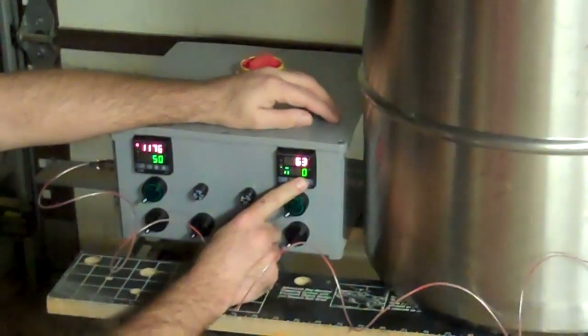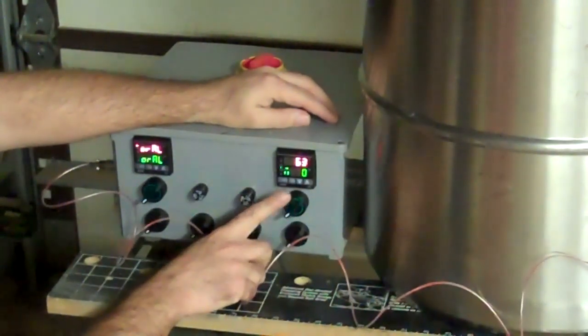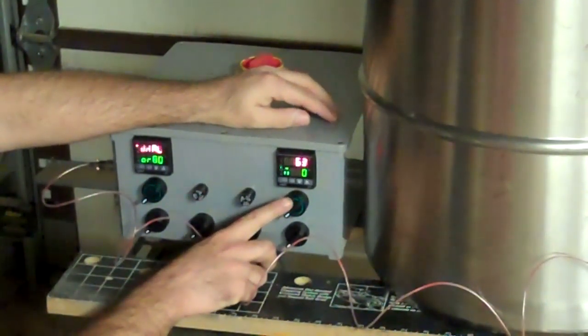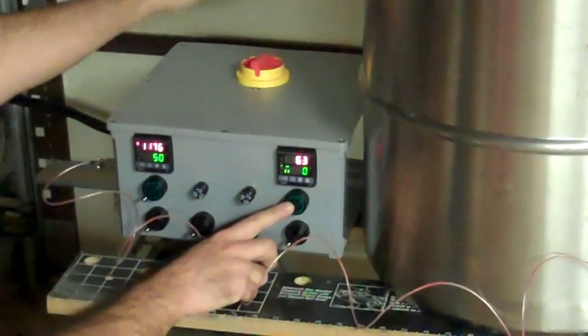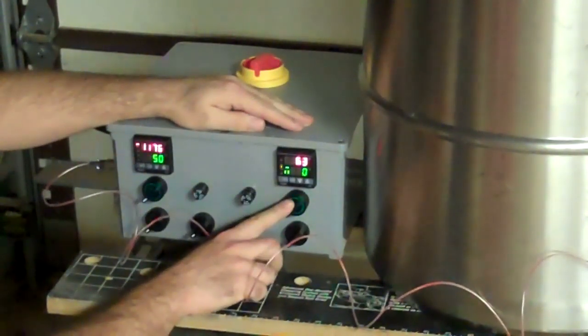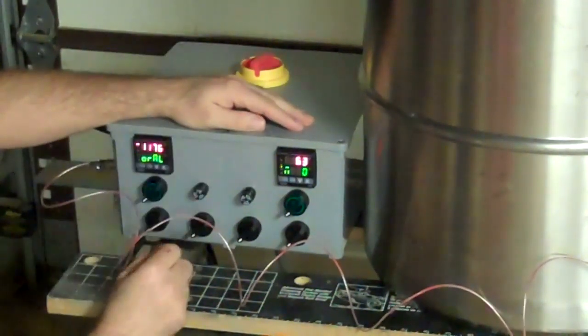So right now it's set at zero, which should mean that we get nothing at the element. This switch runs a relay or a contactor that cuts power entirely to the element. So no matter what this PID is doing, if this switch is off, then there's no power at the element. That's kind of a safety thing.